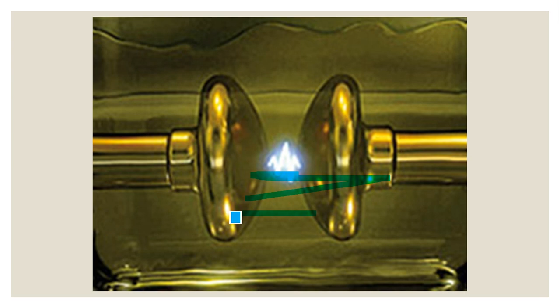We need to measure how much voltage that is. When there is a spark between these two items, we measure that voltage - that is the breakdown voltage of the oil. The test setup looks like this, with two electrodes like this, inside the container. There is a gap of 2.5 mm between the electrodes, and it will be properly set in the chamber.